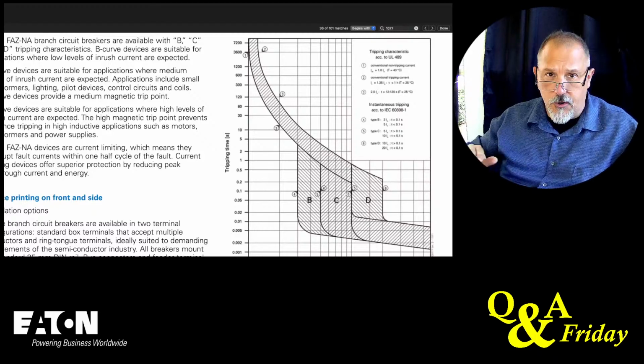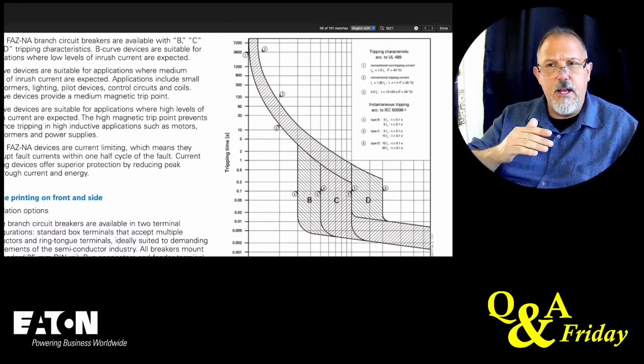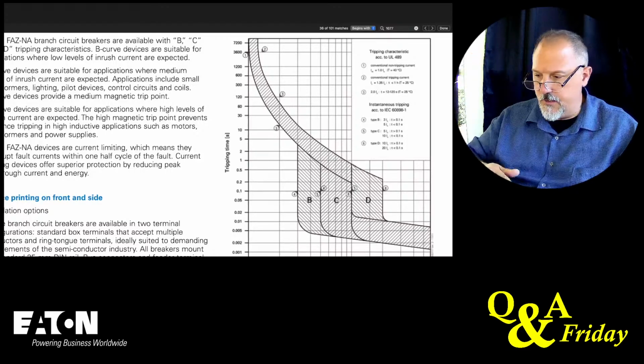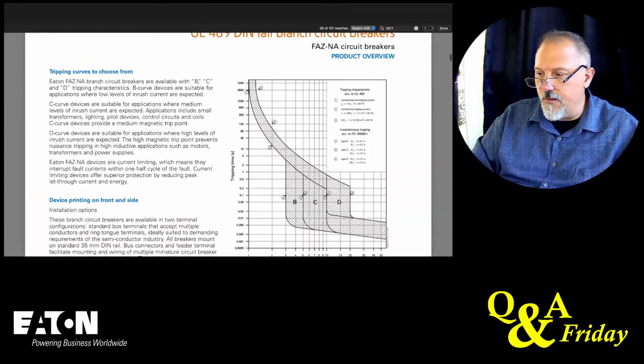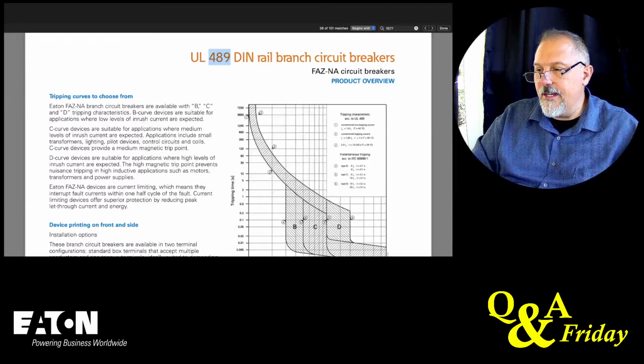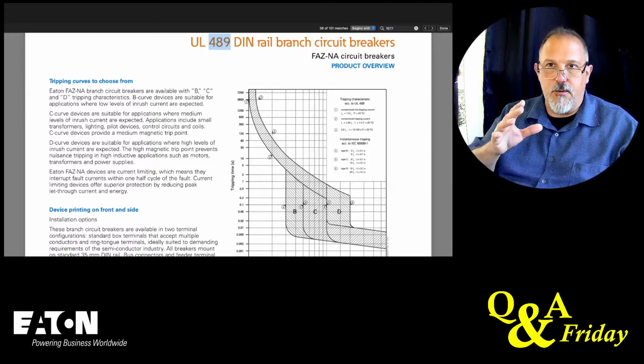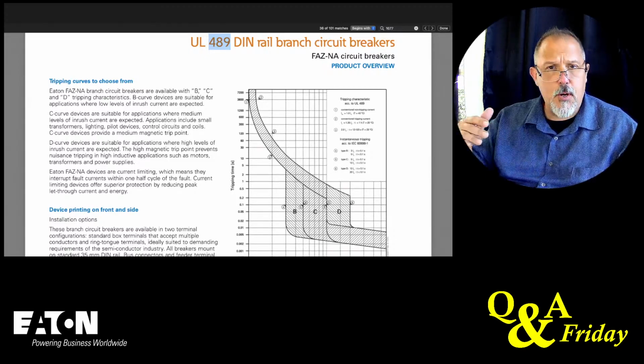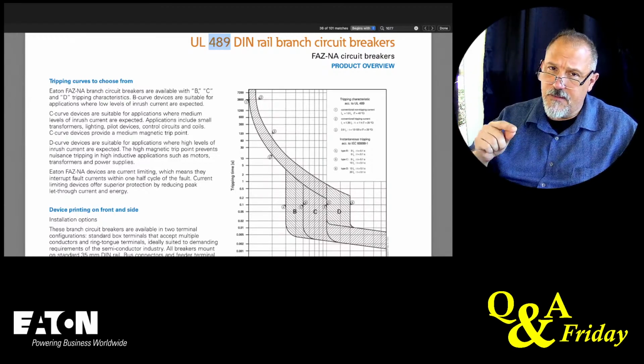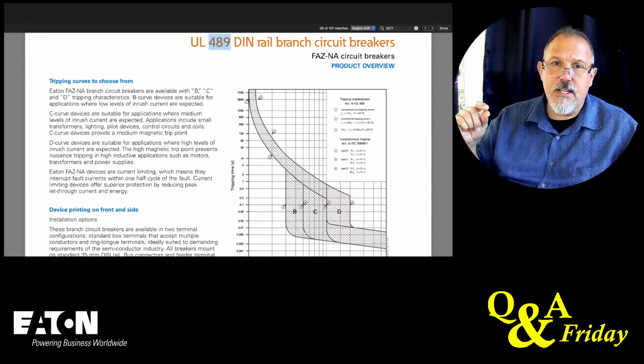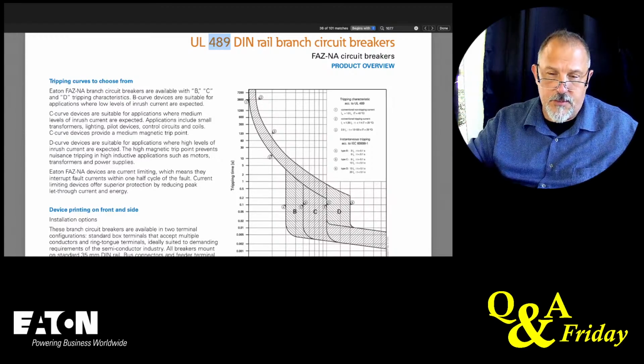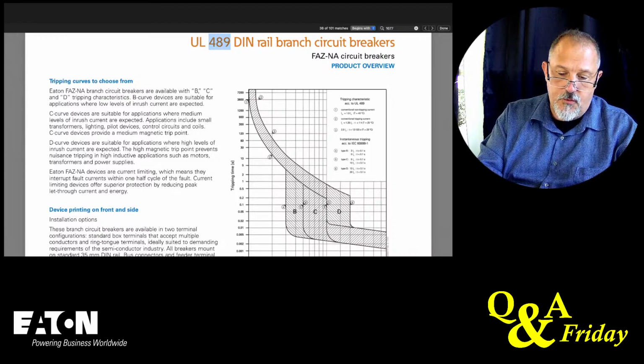So across the bottom we have current, and up the vertical we have time. For increased levels of current, you have faster clearing times. So now his question is, and this is a trip curve for a 489 DIN rail mounted branch circuit breaker. Now we say it's a branch circuit breaker because, per the National Electrical Code, we can use this device to protect branch circuits. The UL 1077 device, since it's not listed to UL 489, is not technically a branch circuit overcurrent protective device, so you can't use that to provide protection for your branch circuits.